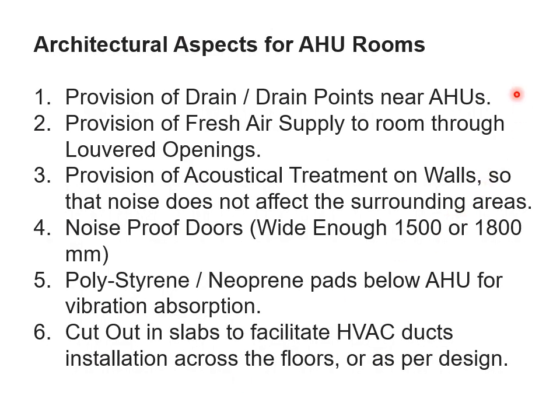Architectural aspects to be considered while planning AHU rooms include: provision of drain points near AHUs, provision of fresh air through louvered openings, acoustical treatment on walls so noise does not affect surrounding areas, noise-proof doors of 1.5 to 1.8 meters width to facilitate movement of large equipment, mounting AHUs over rubber, polystyrene, or neoprene pads to absorb vibrations, and planning shafts or cutouts in slabs to facilitate HVAC duct installation across floors as per design.